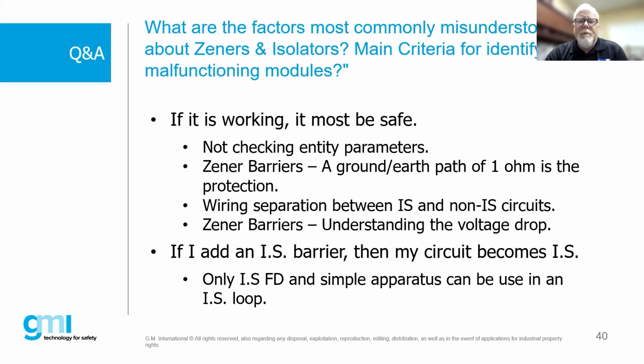The first one is, if it's working, it must be safe, right? I think that's one of the challenges with Zeners, that whether you ground it or not, it still works. Or if your ground is 10 ohms, it still works. So that's one of the misconceptions. Another is not checking entity parameters. A lot of customers say, I have my IS field device and I have a barrier, boom, done, I have IS protection.